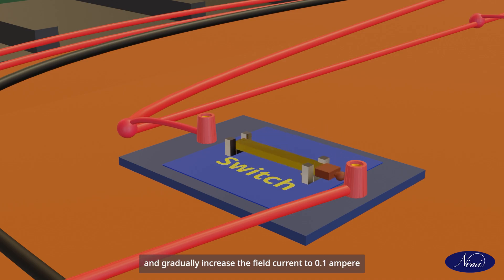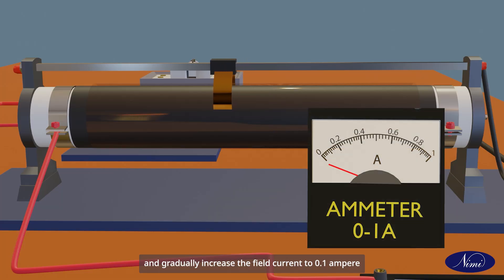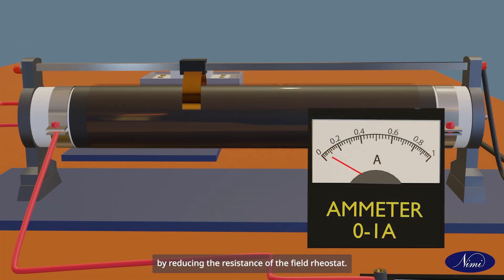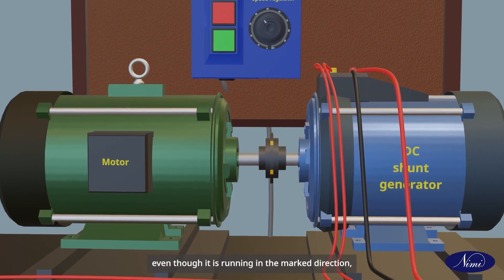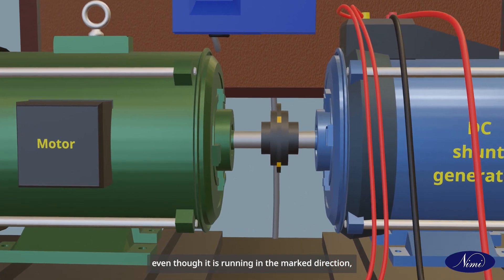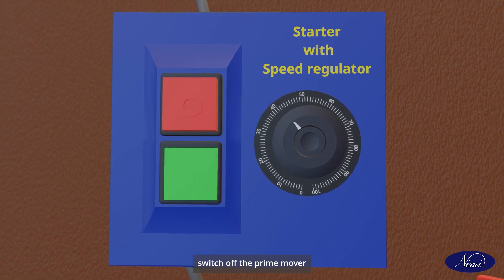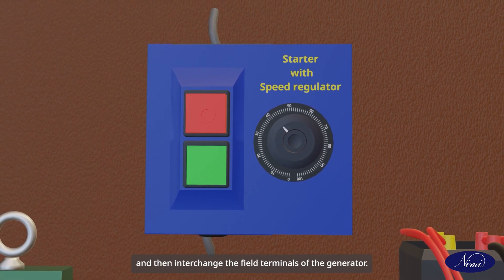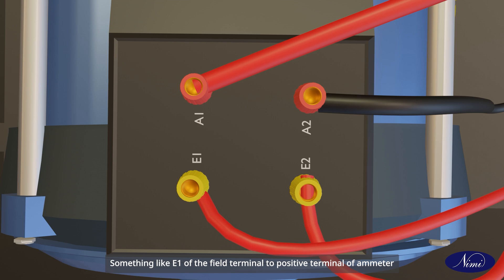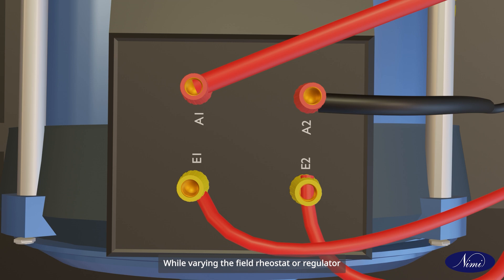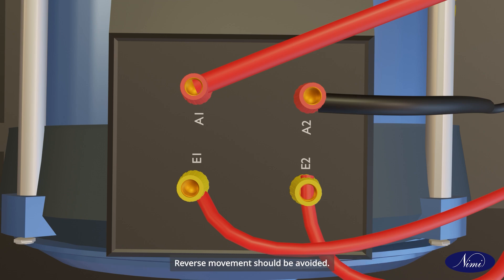Close the field circuit switch and gradually increase the field current to 0.1 ampere by reducing the resistance of the field rheostat. If the generator is not able to build up voltage even though it is running in the marked direction, switch off the prime mover and then interchange the field terminals of the generator — something like E1 of the field terminal to the positive terminal of the ammeter and terminal E2 to the switch. While varying the field rheostat or regulator, it should be done positively and slowly in the forward direction; reverse movement should be avoided.